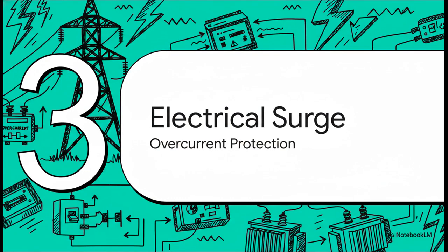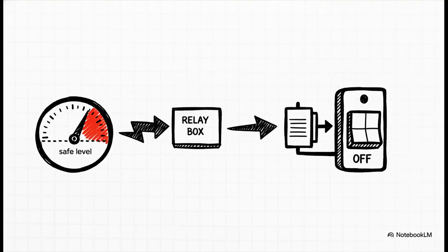Okay, let's dive into that first layer of defense, the electrical protection. We're going to look at a classic example, a device called an overcurrent relay. Its whole job is to stand guard against those dangerous electrical surges. The idea here is actually super simple, but it's brilliant. The system sets a safe maximum level for the electrical current. If the current flowing through that transformer ever goes above that preset limit, that digital tripwire, it instantly fires off a signal to a circuit breaker and disconnects the transformer from the power grid.